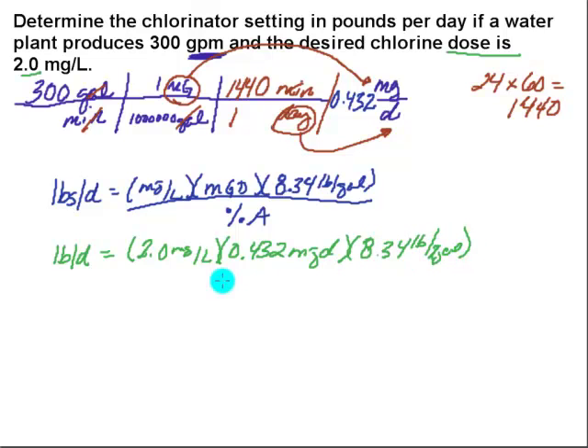And we're going to divide by the percent of available chlorine. Now in this case, they didn't actually tell me any percent available chlorine, and it does say the chlorinator setting. So I'm going to assume that we're using chlorine gas, which is 100%, but this percent always has to go in as a decimal. So this is just going to become a 1 down here on the bottom.